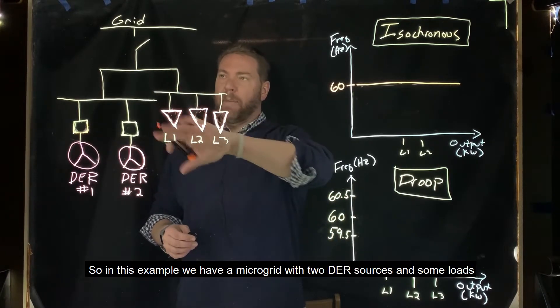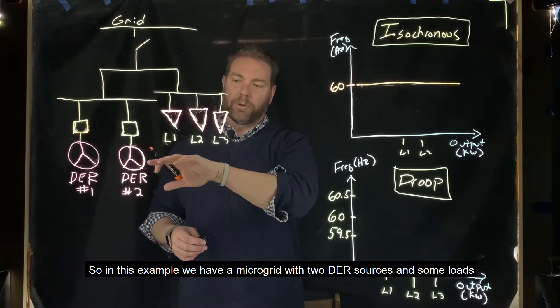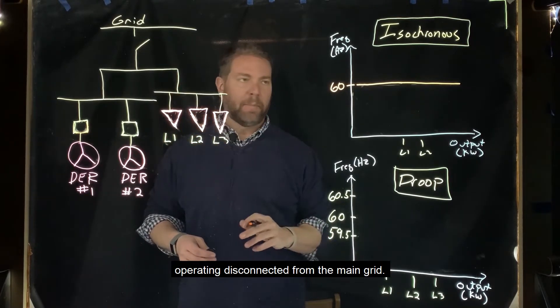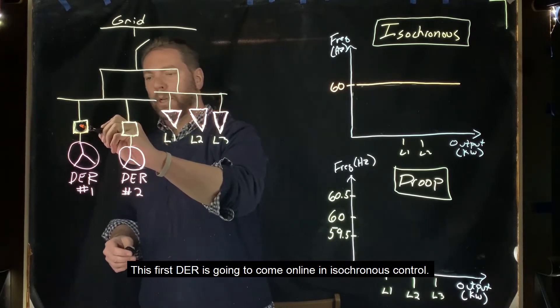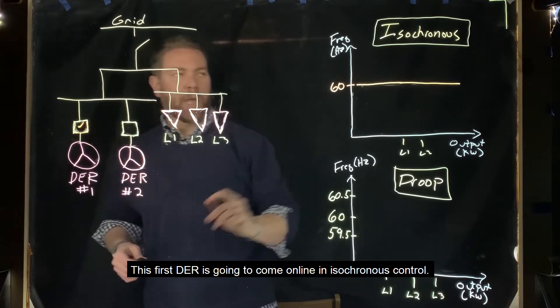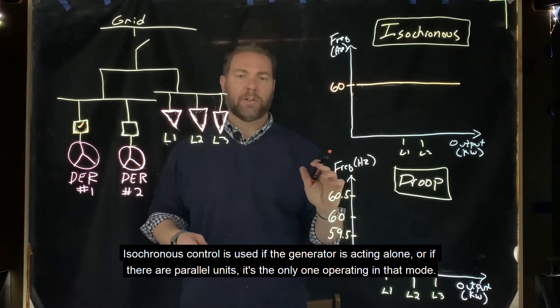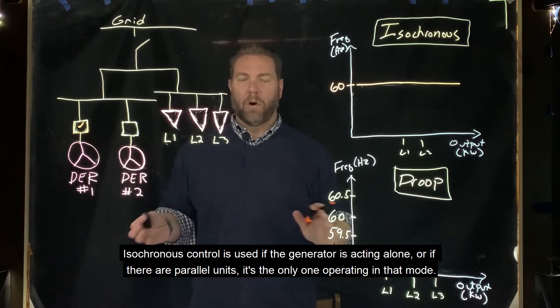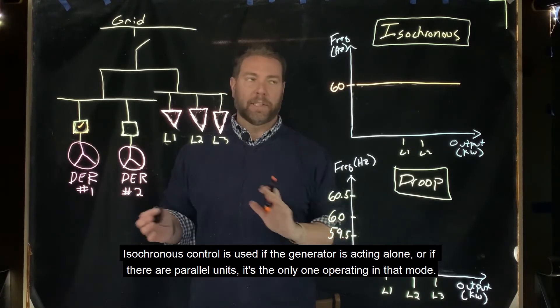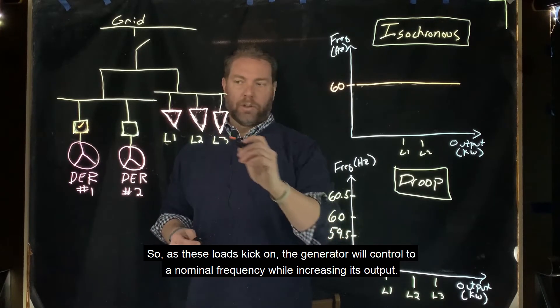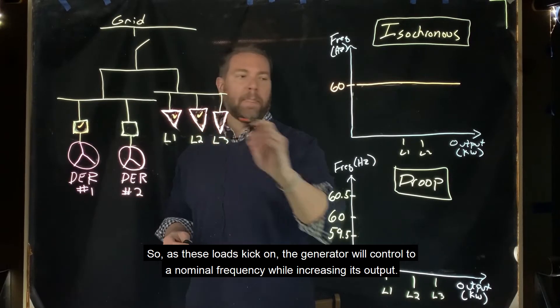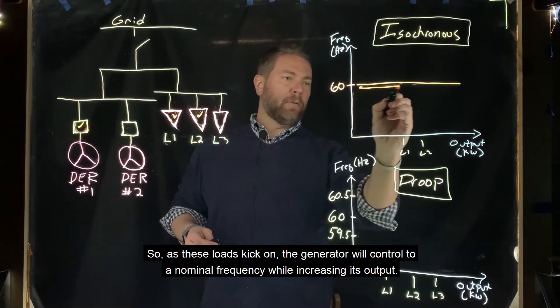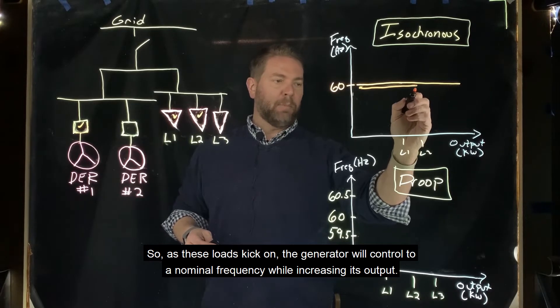In this example, we have a microgrid with two DER sources and some loads operating disconnected from the main grid. This first DER is going to come online in isochronous control. Isochronous control is used if the generator is acting alone, or if there are parallel units, it's the only one operating in that mode. As these loads kick on, the generator will control to a nominal frequency while increasing its output.